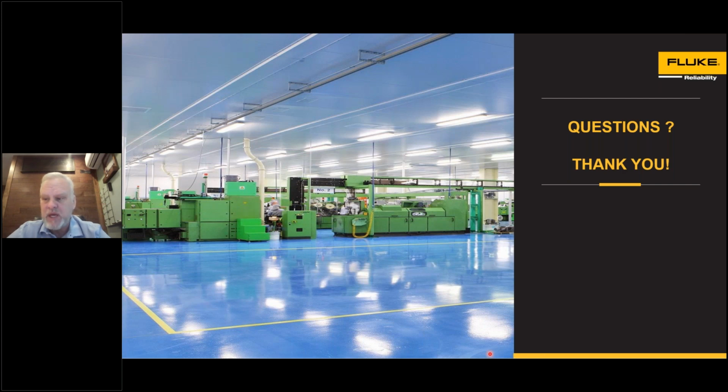Again, as I mentioned, we have a lower frequency version of this sensor coming, so tune in soon. We're pulling many of those machines up into our application list as we speak. But one of the things I might avoid would be head shafts and tail shafts on conveyors if they're below 600 RPM, and most are. Maybe that would be an online system currently, or as we get better resolution into that low frequency range, they will become a better application for our wireless sensor. Yes, thank you.